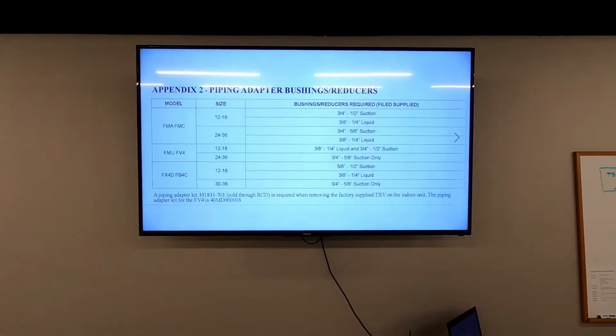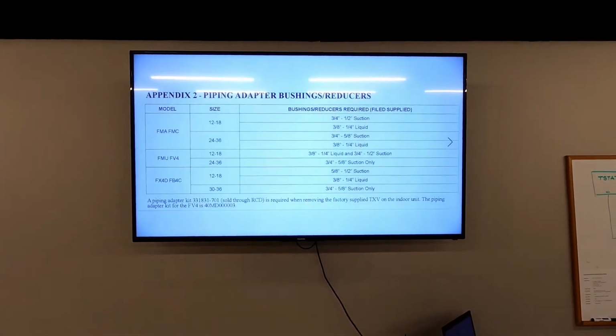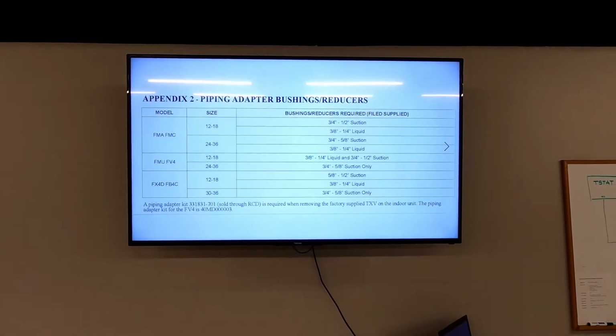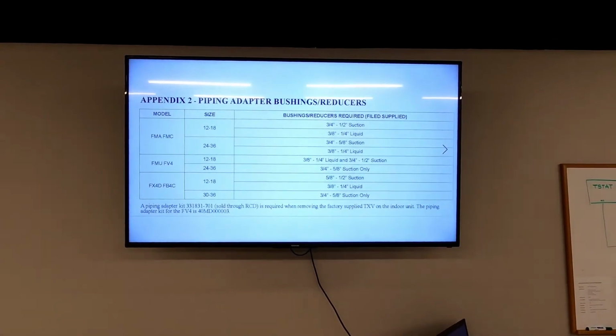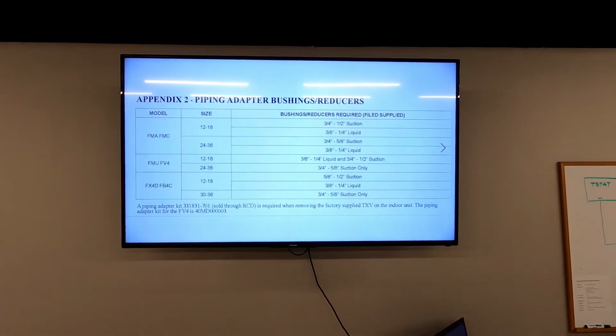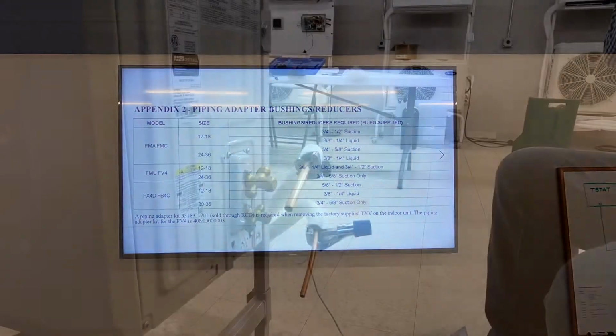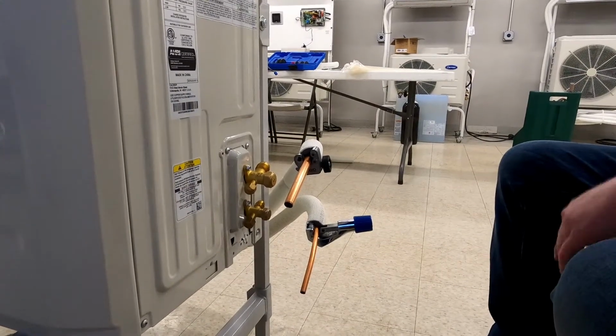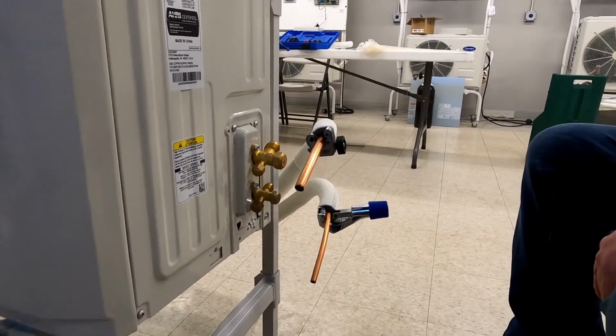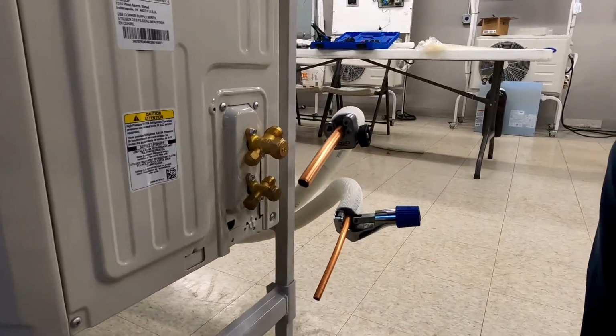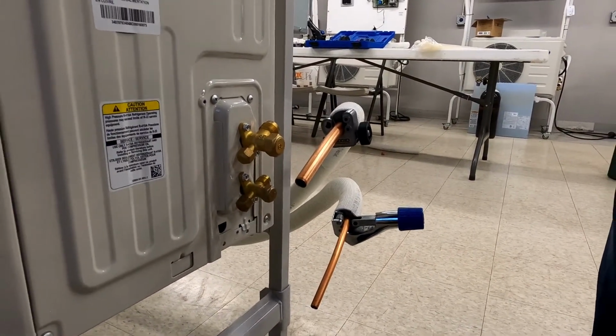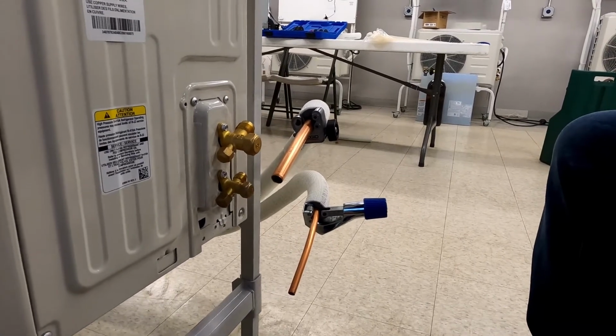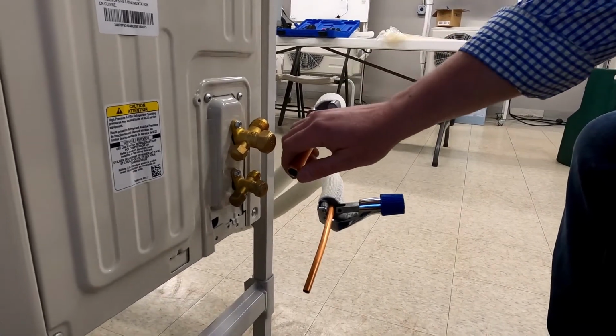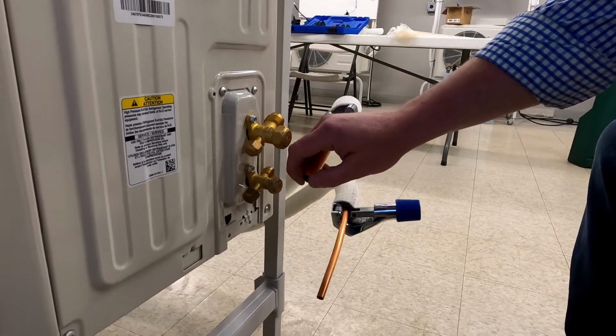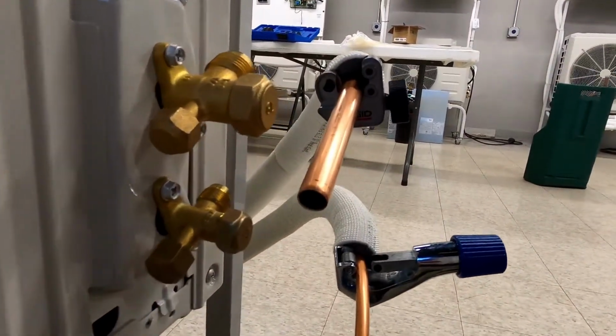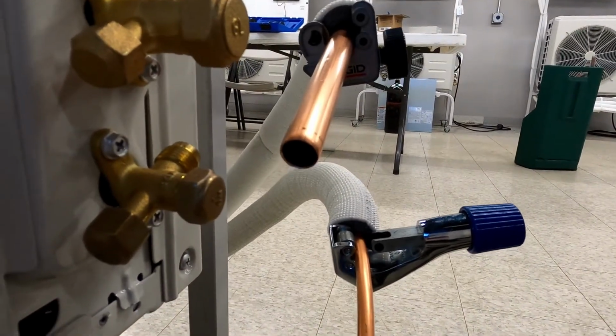Depending on the combination of indoor and outdoor units that you have, you may need to get reducers for the line set. You always run the line set in the size that it connects to the outdoor unit. Now that we have our line set run, we're ready to do one of the most important steps in the installation, and that's making the flare connections at the outdoor unit. The first step to making an effective flare is to make sure that when you cut the pipe that you cut it square and as clean as possible. That'll give you the best chance to have a leak-free flare the first time.